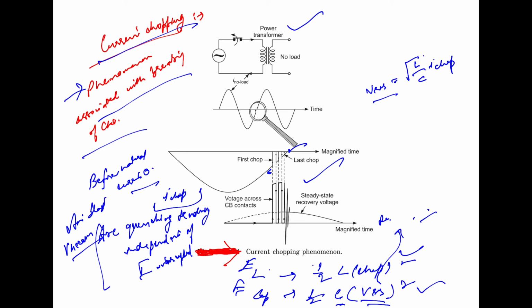Now from this figure, there will be multiple chopping of the current, along with large overvoltage, till the current finally reaches the natural current zero. Such overvoltages are harmful for the circuit breaker itself as well as for the other power system elements. So in an ideal circuit breaker, the arc must continue till the current reaches natural current zero, and the composition of the contact material of the circuit breaker also plays a very important part in maintaining the arc till the natural current zero.